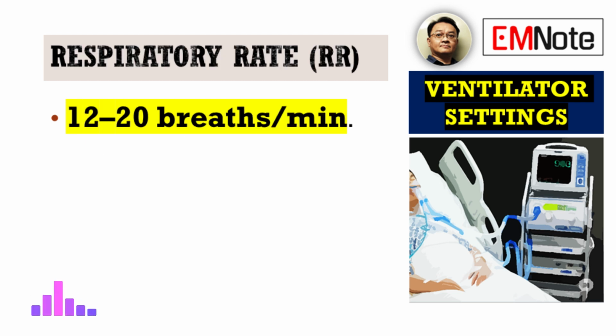Next, the respiratory rate. What's the typical starting frequency for breaths per minute? The respiratory rate, or breathing frequency, is typically set somewhere between 12 to 20 breaths per minute for an adult patient. This establishes a baseline breathing frequency, ensuring adequate minute ventilation, that's the total volume breathed per minute, and carbon dioxide removal. It provides a controlled, rhythmic breathing pattern that supports gas exchange. And this rate, of course, will then be adjusted based on the patient's carbon dioxide levels.